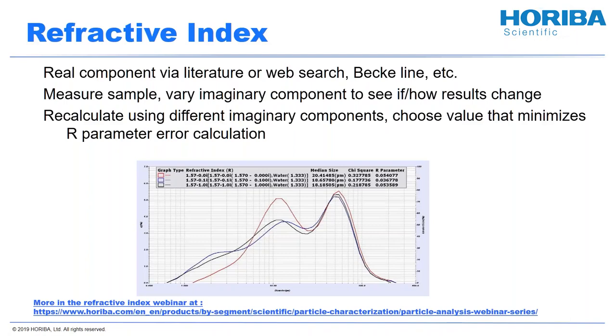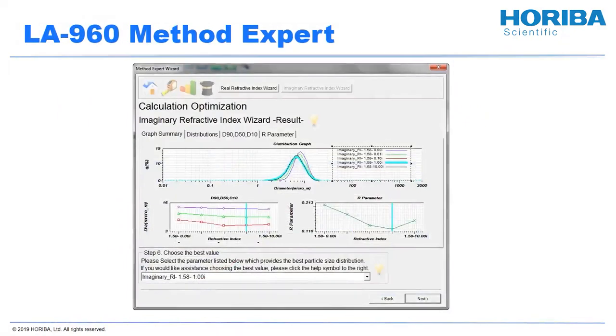We have a tool for doing this in the LA 960 called the Method Expert. I tell it the sample I'm going to work with and the range of refractive index values to try. It generates distribution graphs for each of the real and imaginary refractive index values tried, plus a plot of diameter as a function of refractive index and R parameter as a function of refractive index. Then I can look at those plots, pick the value where the R parameter is minimized, and select my imaginary refractive index.